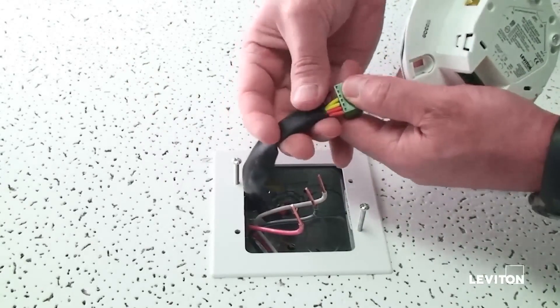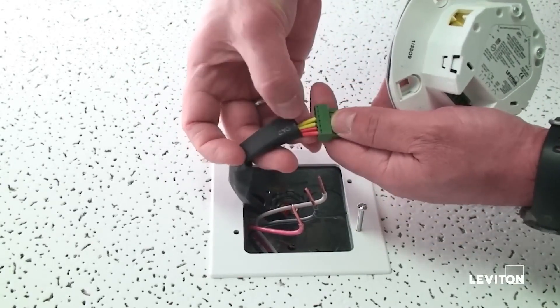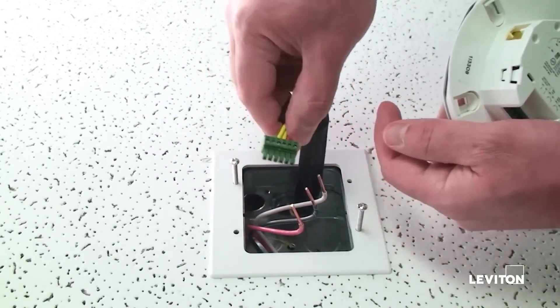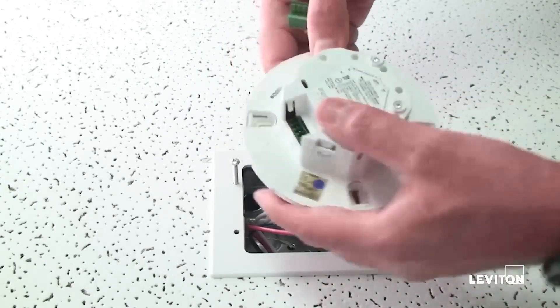To install the switch or BMS interface, you need four low voltage wires — two for the switch interface and two for the BMS interface. Wire these into the connector provided in the box. The low voltage connector connects at this location.